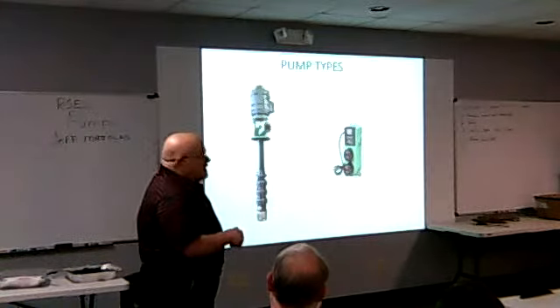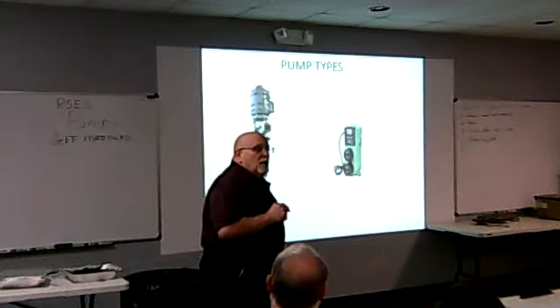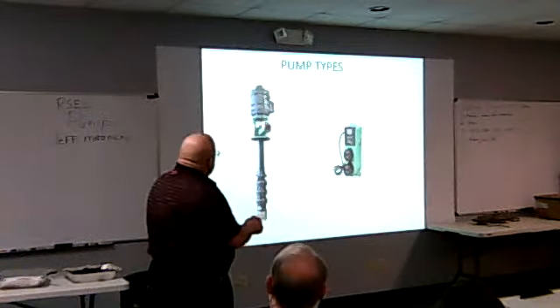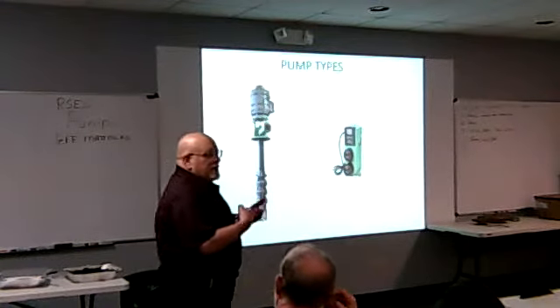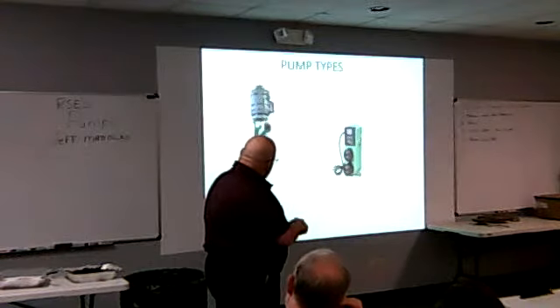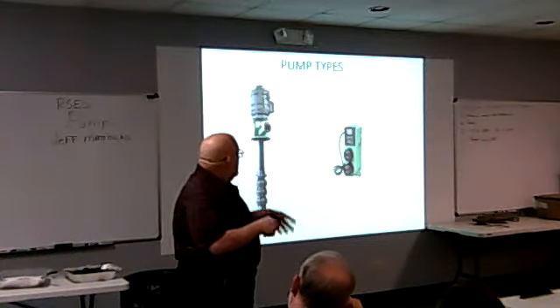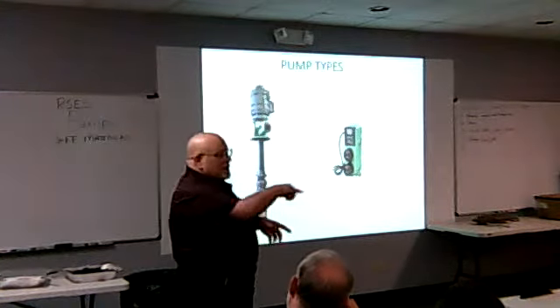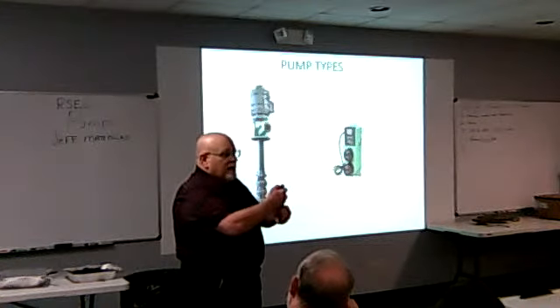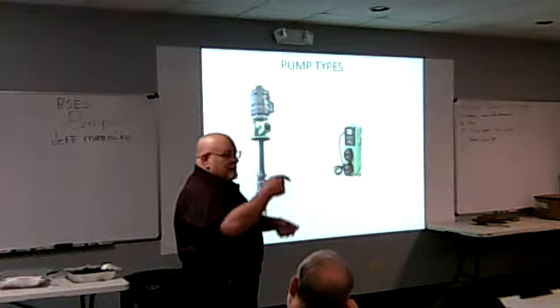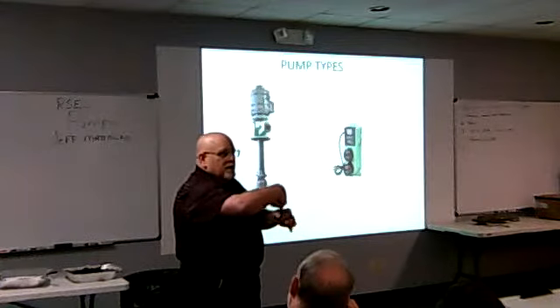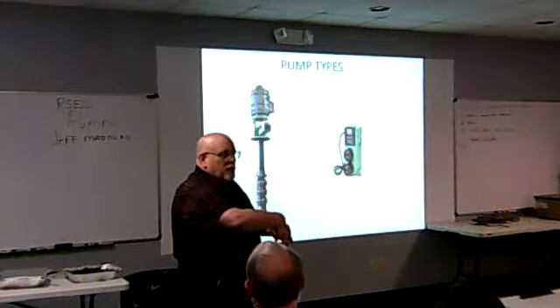This is a more residential. A keyed hollow shaft or? Yeah, what it is up in here, they actually have a coupling down here, it's got a vent with it. The shaft will actually be down on the ground. When you set these up, you take the shaft up here and you spin it, get it to lock, you go face to face. Then you tie in a gib key on the top. There's a slot, there's a groove in the shaft with a gib key that goes in.